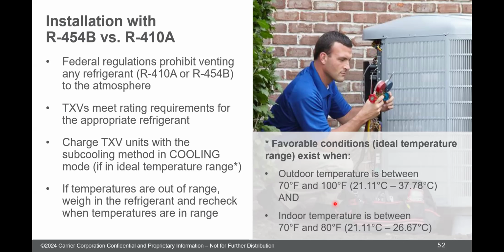No change there. And just like with 410A, they want you to charge it with the indoor and outdoor coil being more than 70 degrees. It's always easy to get the indoor coil above 70 degrees. Just run the heat for a while, and then the room will warm up, the building will warm up, and then you'll be above 70. Outdoors is harder. You're not going to warm up the whole outside.